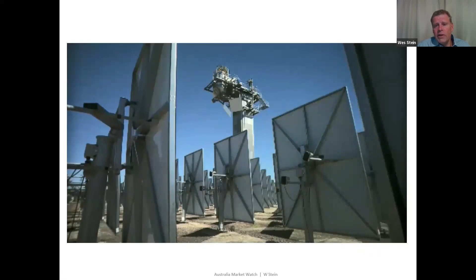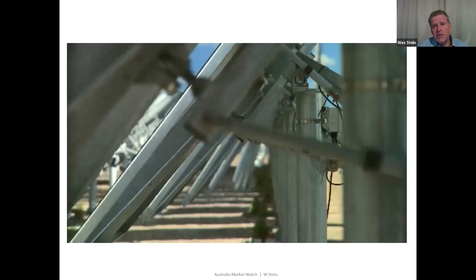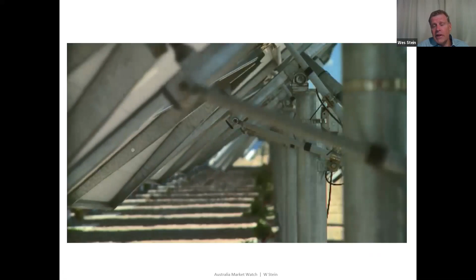We have relatively small heliostats compared to what's available in the rest of the world. Our heliostats are 5 to 7 square meters each. We concentrate on receivers operating at around 700 degrees C or even greater. Because of that, we need quite small receiver target areas. The apertures in this particular case are only one square meter. And that's the other reason for having small heliostats, that we can then get that concentrated energy into that very small aperture. In this case, we're running a supercritical CO2 receiver at around about 720 degrees Celsius.